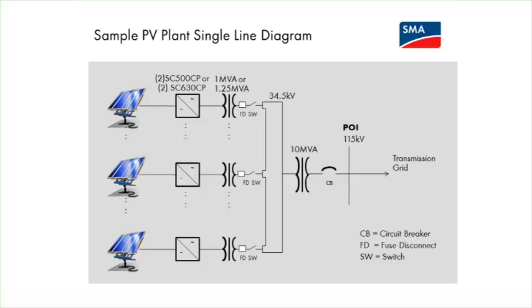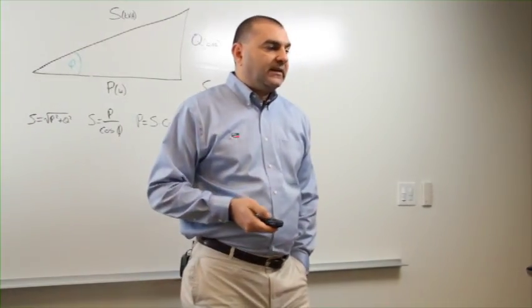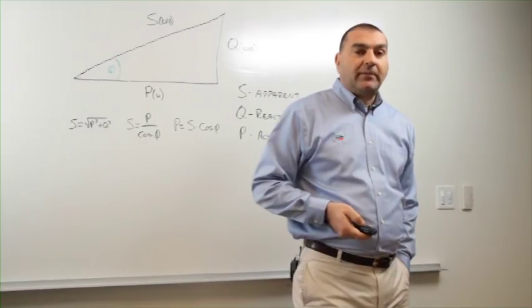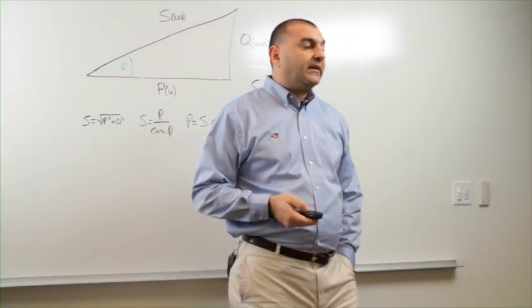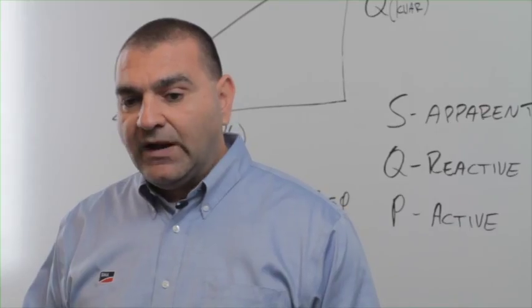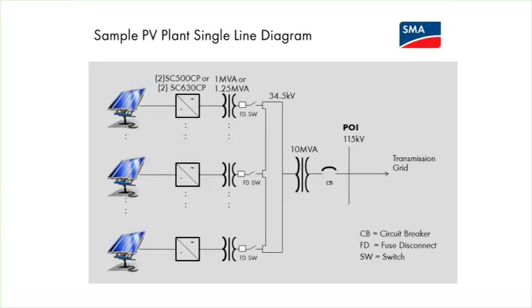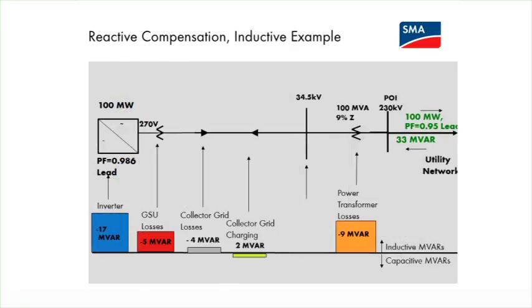So the point of interconnection that the utility cares about is basically at the 115 point common coupling, the common point of coupling. So why is that important? That's because if the utility requires a 0.95 lead power factor at the point of interconnection on a 100 megawatt plant, for example, there's a lot of VAR compensation that needs to come into play. There are what we call GSU losses. There are the step-up transformer losses from medium voltage to high voltage. There's the grid charging. There are losses in the cables, etc.